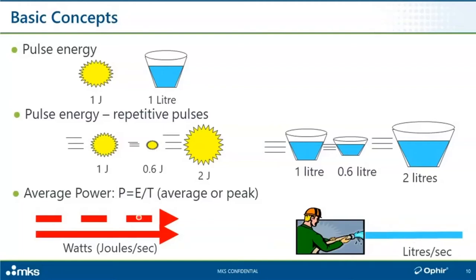I should mention that in some applications, users typically refer to peak power. What we mean in our segment of the industry by peak power is the instantaneous power during the course of a pulse. For example, going back to that one-joule pulse coming in once per second — average power is one watt. But if we zoom in on one of those pulses and that pulse is, say, one millisecond long, then during the course of that millisecond the instantaneous or peak power is one joule per millisecond — that's one kilowatt. So peak power during the pulse is one kilowatt, but average power is one watt. If you remember that, it could help you avoid a lot of confusion.